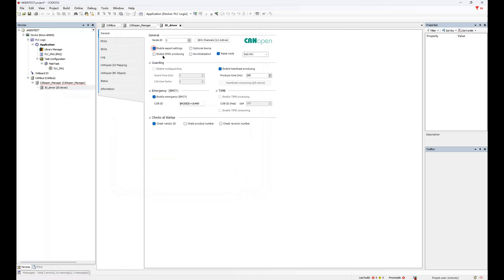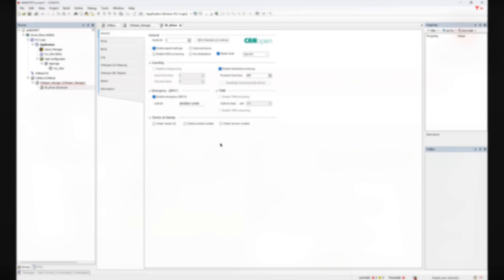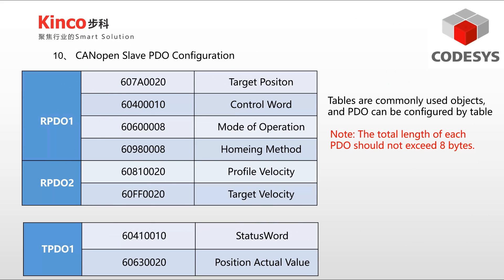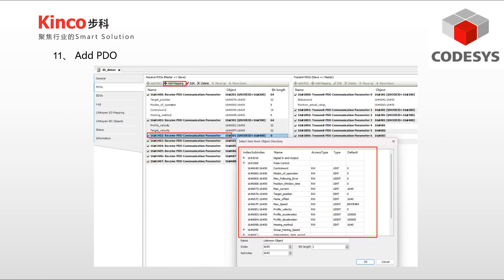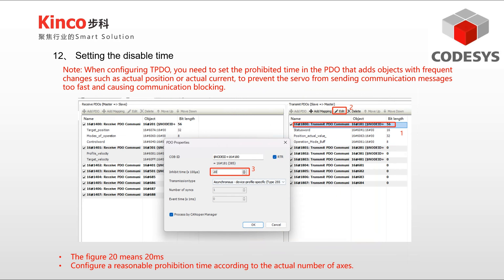I recommend enabling the Expert Settings and unchecking the Check Vendor ID function at the bottom. These are the commonly used PDO configuration parameters, which can be set according to the actual needs of the control object. Redundant PDOs will occupy bus resources, and please note that the maximum length of PDO is 8 bytes. It is also necessary to set an inhibit time to avoid excessive communication speed occupying excess bus resources.